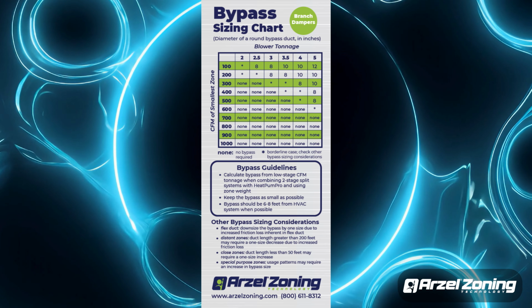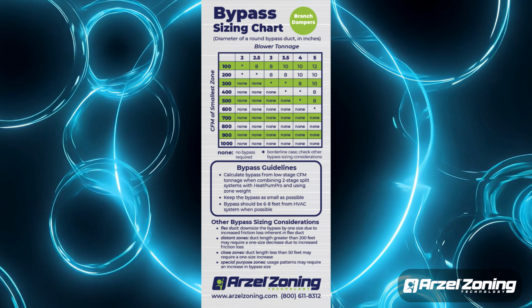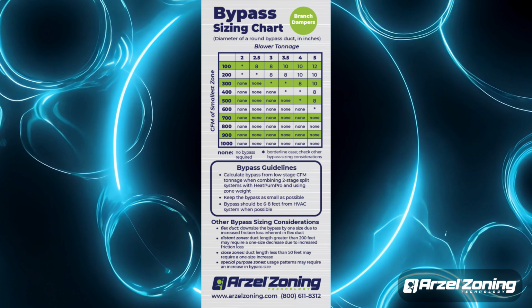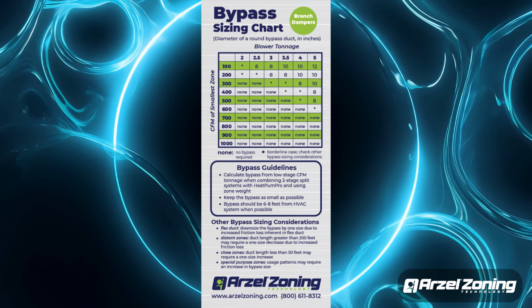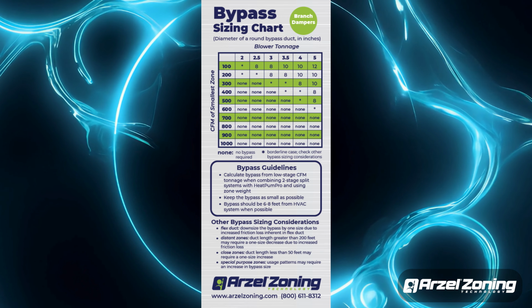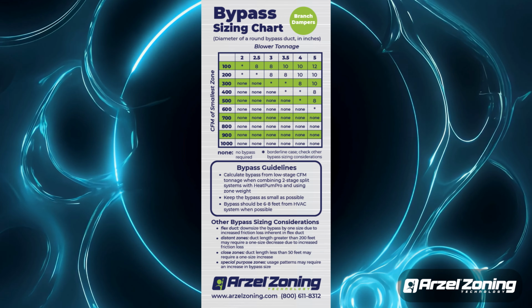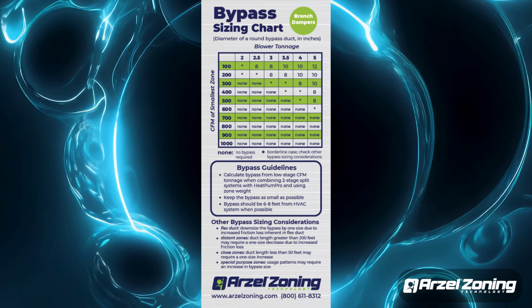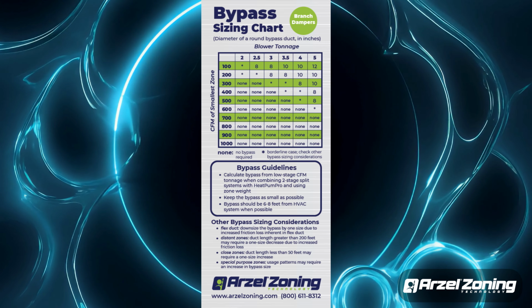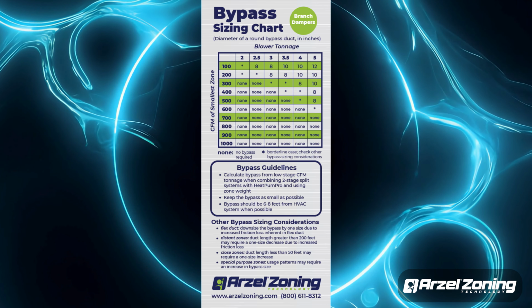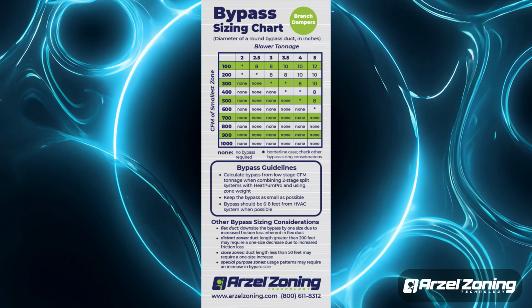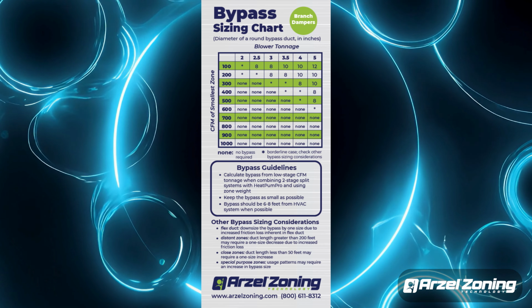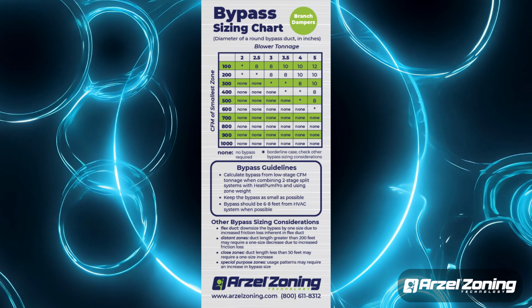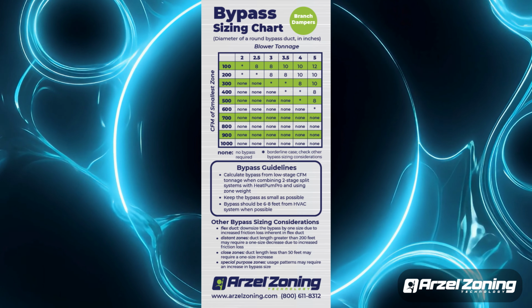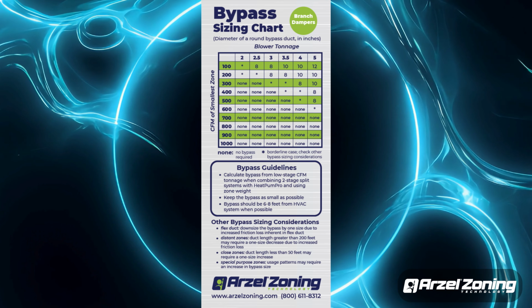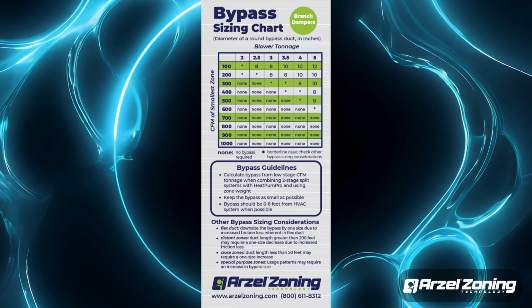Why am I using the biggest bypass our zone makes residentially? It's probably because I created a really small zone on a fairly large piece of equipment. I should probably try and get more supplies on there or make that zone bigger. If I need a 10, it's probably okay. If I need an 8, you know what, that's totally fine. A little bypass is not a bad thing. While a lot of our systems, especially if they're multi-stage and it's on the Heat Pump Pro, don't need a bypass at all. If all you need on your system is an 8 inch, yeah, that's fine. That's not very much bypass at all.